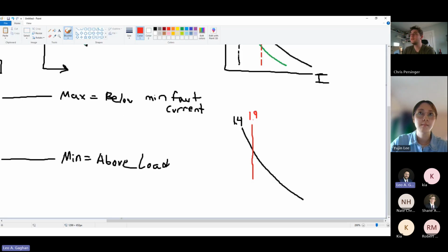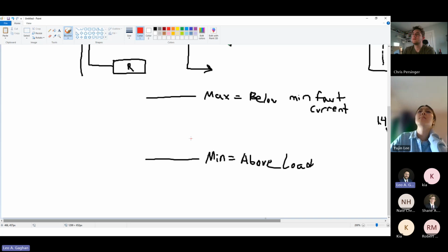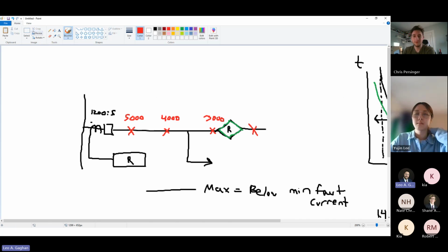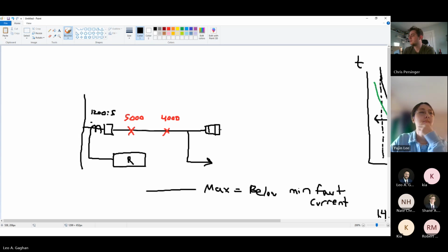So let's say the situation, let's say that wasn't a recloser. Let's say that was a fuse. That's more what a fuse looks like, and it's got its own load down here. So if a fault were to happen right here, let's say it was a temporary fault. A temporary fault happens right here. That fuse, if it blows, those people are going to lose power, and their power is going to be gone until a technician gets out there and replaces that fuse.